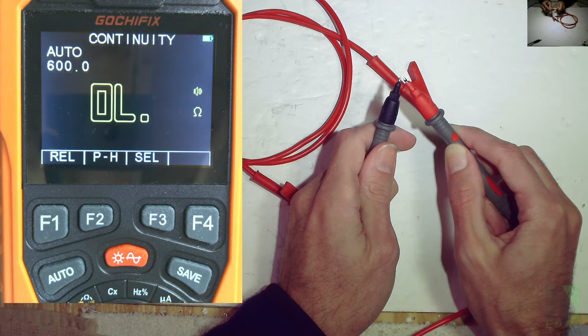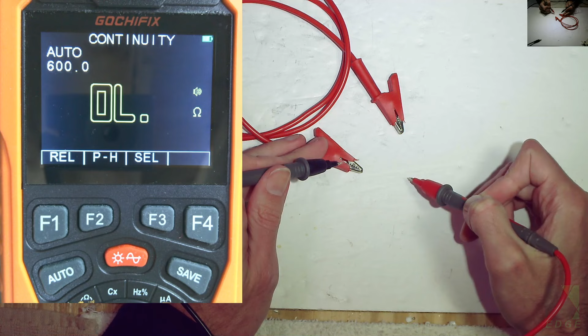You can see that whenever I touch the probes, instantly there's a beeping sound, and that indicates continuity. Let's pretend these alligator clips are a cable running underground, maybe a solar panel feed, and we're not sure if there's a broken wire. We can check one side of the conductors, positive or negative, to see if there's a break. I'll touch the probes, and you'll see there's a continuous tone.